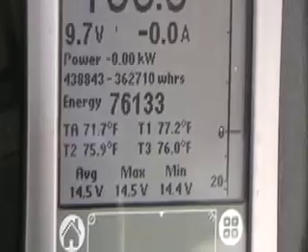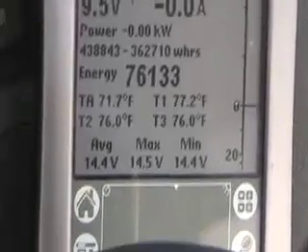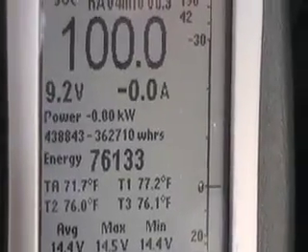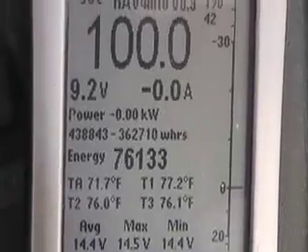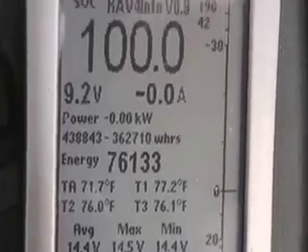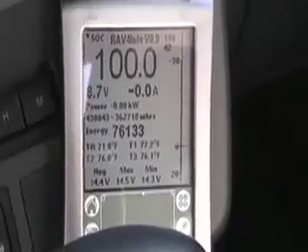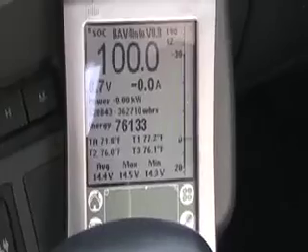Leveling is a very misunderstood process. We can't look down to the cell level. To really charge these batteries optimally, we'd have to go down to the cell level and look at the dV/dt — the time when the voltage goes up to a maximum of about 14.6 and then goes down slightly. That's when it's 100% fully charged. We can't do that with these batteries because we are dealing with modules that have 10 cells each.